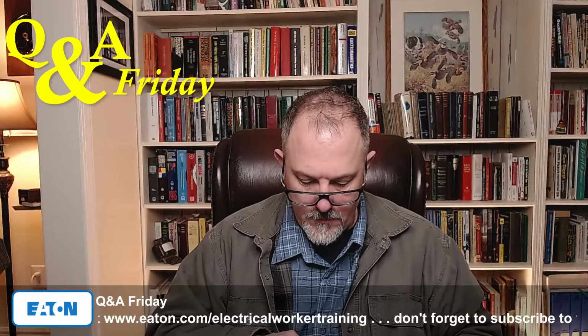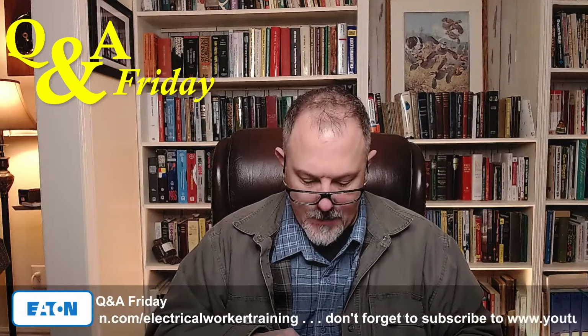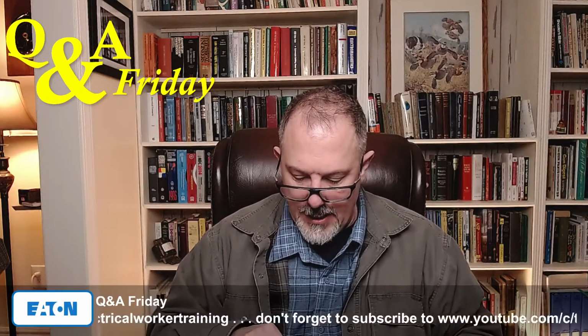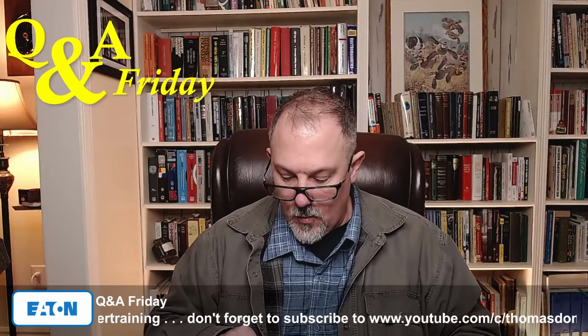It says in note 1 on table 9, these values are based on the following constants: UL type RHH wires with class B stranding in cradle configuration. Wire conductivities are 100% IACS copper and 61% IACS aluminum, and aluminum conduit is 45%. Capacitive reactance is ignored since it's negligible at these voltages.